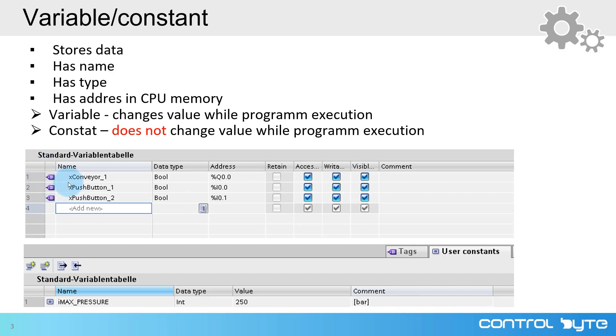Here you can see the tag table with some variables defined. I have defined a variable for the conveyor — this is the output variable — and I have defined two variables for push buttons. All those variables are declared as boolean data type, which means they can have a value of zero or one, true or false. Here you can see the address of those variables. X_Conveyor1 is declared as an output variable at address 0.0.